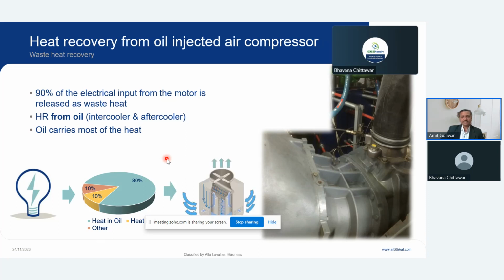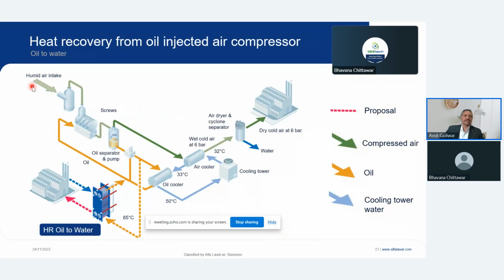How can it be recovered? It can be recovered by this schematic. A typical case is humid air comes into the separator, goes into the screw, and then after separation, air goes to the air cooler and oil goes to the oil cooler. What we can do is take a tapping after a control valve, and this oil can go to a heat exchanger, and from this heat exchanger you can generate water at a high temperature, I mean, at 40, 55, 60, 65 degrees. This water can be used for boiler feed water, in the canteen, or in any process wherever it is possible. And this is basically a bypass to your existing heat exchangers. So even if you have an existing compressor, you can very well recover the heat.